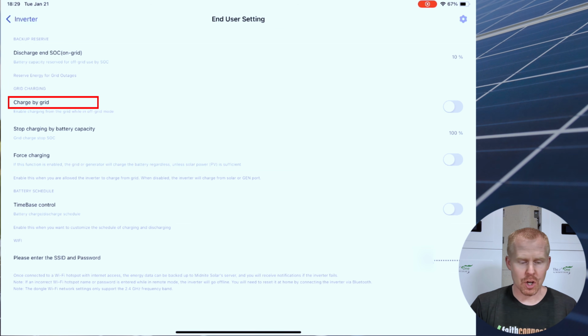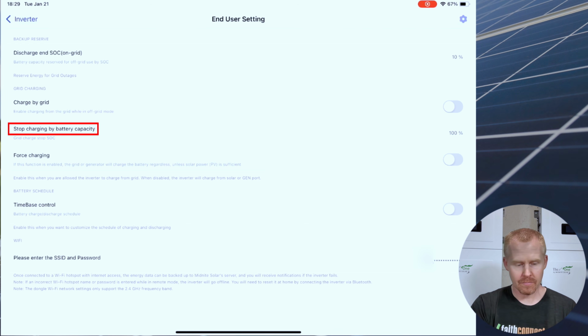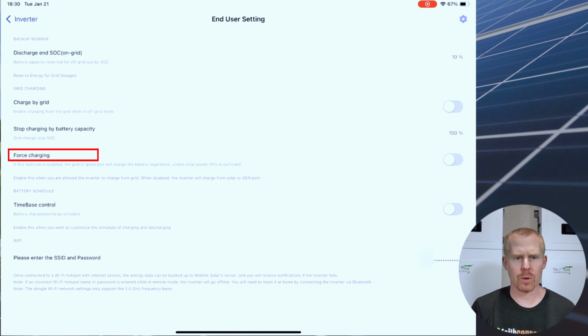The next option is charge by grid. You can toggle this on and off, whether or not you want to be able to charge from your AC input connection. And then the next option, if you're charging from the grid, is the state of charge at which you want to stop charging from the grid. I believe that force charging is going to tell your system to charge regardless of the state of charge. Now, I believe you do have to be in a grid mode, where your inverter is running off of grid power, for this to work.